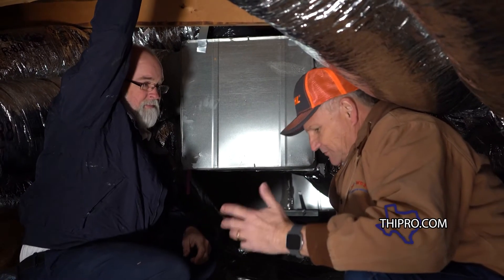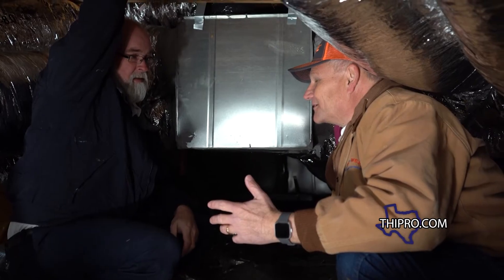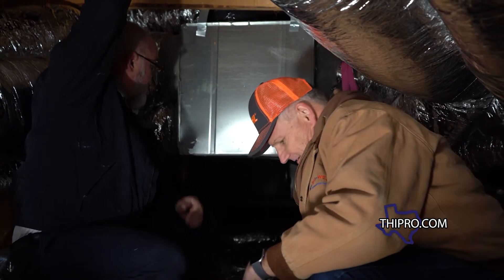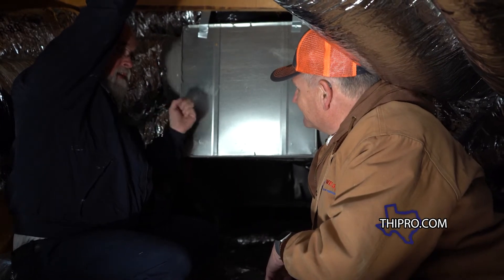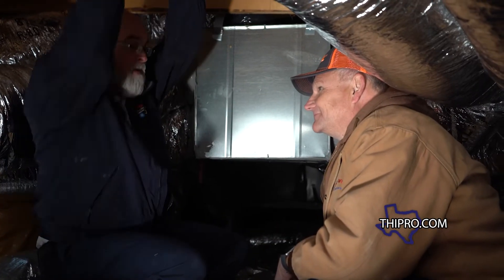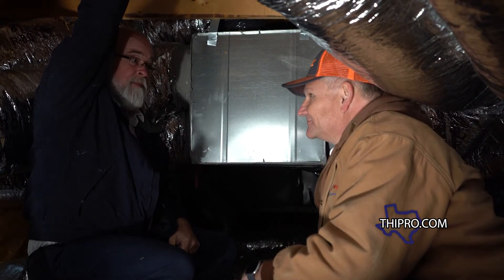A lot of times people don't realize, but some of the old ductwork is losing 20% of their air to leaks — that's really running up electric bills. What they also don't realize is if you don't seal the return air side where it's sucking air in, you're getting insulation and dust into your system, which runs your electric bill up even more when it gets dirty. And it runs that dust out into the house as well — so mama's not happy.